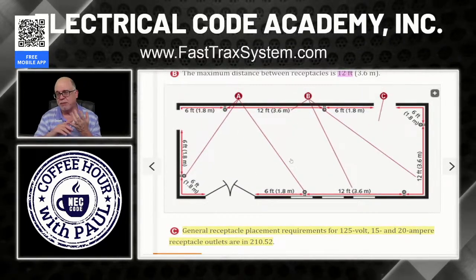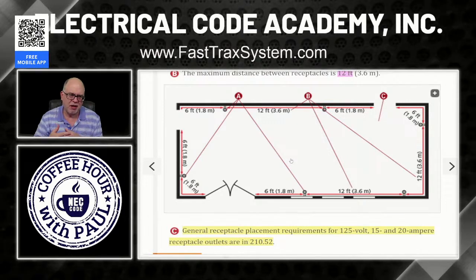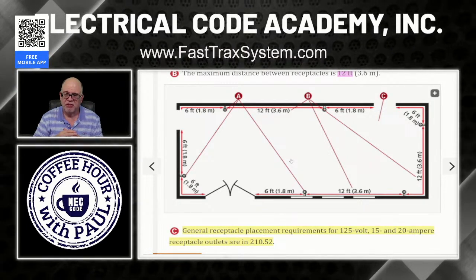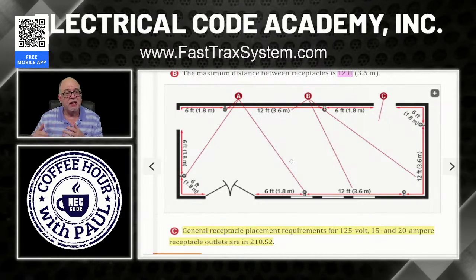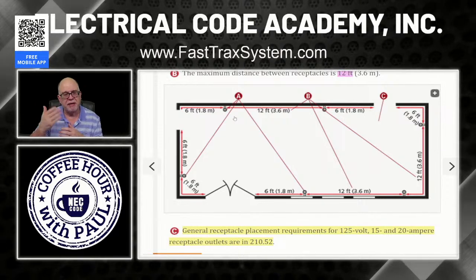Very common in bedrooms, especially when you're doing the efficiency homes where they're trying to keep the costs down and they might not want to put luminaires in the rooms. Well, they still have to have something switched in the room, right? So it's either a switched luminaire or they can switch a receptacle. You just can't switch the entire receptacle. You can switch half of it and leave the other half hot, and the hot part would meet the spacing requirements, and then the other half meets the switching requirement in lieu of the lighting outlet.